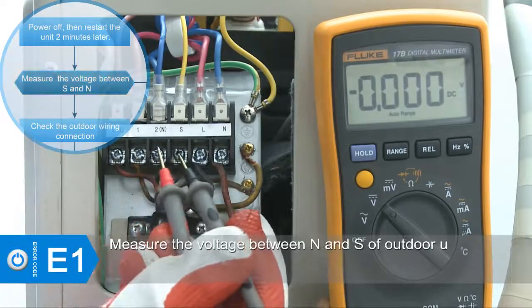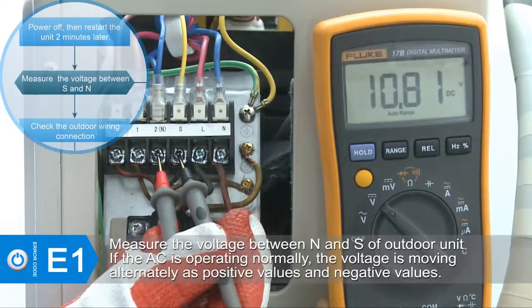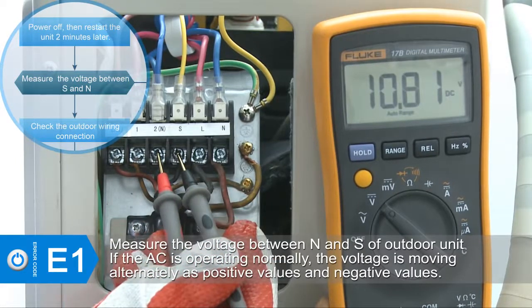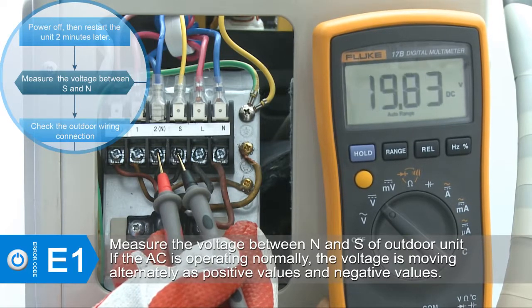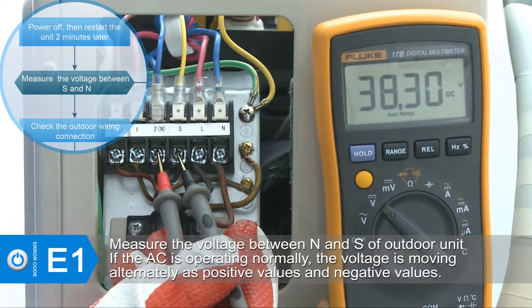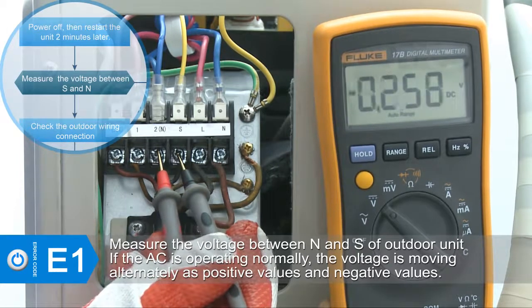Measure the voltage between N and S of outdoor unit. Select voltage DC position, then connect the red pin of multimeter to N ports, the black pin to S port. If the AC is operating normally, the voltage is moving alternately as positive values and negative values.